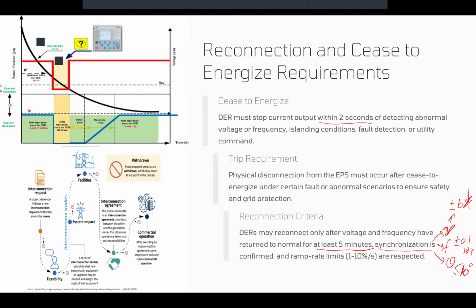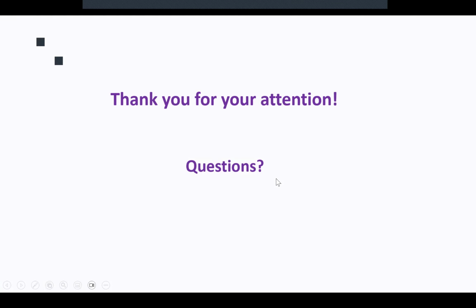Now, we said after those conditions, 5 minutes of healthy grid and the synchronization, we can start the reconnection, but it should be a ramp rate increase in power, which by default is 1% per second. You can adjust this 1% in an interval of 0.5% to 10% per second. So you can go faster, up to 10% per second, and you can go slower, down to 0.5% per second. Okay, this is the discussion that we have for IEEE 1547, which defines the requirements for integration of the distributed energy resources.